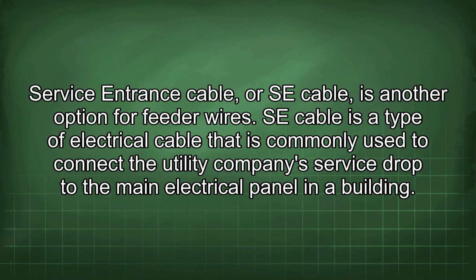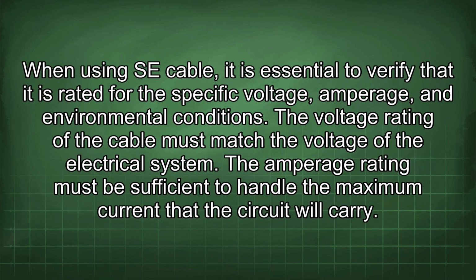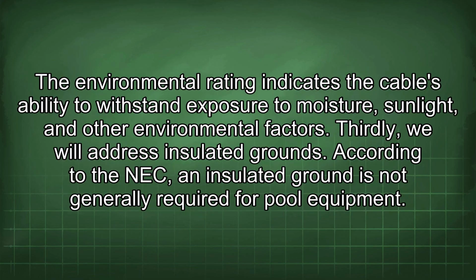Service entrance cable, or SE cable, is another option for feeder wires. SE cable is a type of electrical cable that is commonly used to connect the utility company's service drop to the main electrical panel in a building. When using SE cable, it is essential to verify that it is rated for the specific voltage, amperage, and environmental conditions. The voltage rating of the cable must match the voltage of the electrical system. The amperage rating must be sufficient to handle the maximum current that the circuit will carry. The environmental rating indicates the cable's ability to withstand exposure to moisture, sunlight, and other environmental factors.